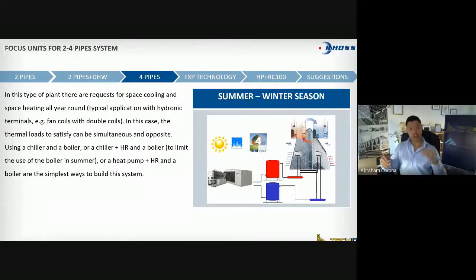You can start to use a chiller with heat recovery, and that will give you a little better efficiency, but you may need a boiler when you need heating only. I say that because when you're not using an EXP polyvalent system type, that we're going to explain in the next slide, if you have a chiller with heat recovery or a heat pump with heat recovery, there is something important you need to imagine. There are 2-pipe systems, that means heat recovery. But if for any reason you want only heat, you cannot get only heat, because you need a demand of cooling to be able to get heat recovery.